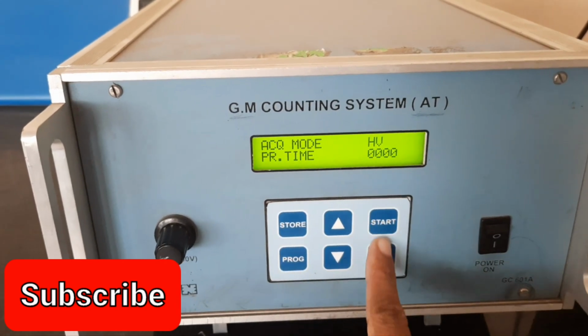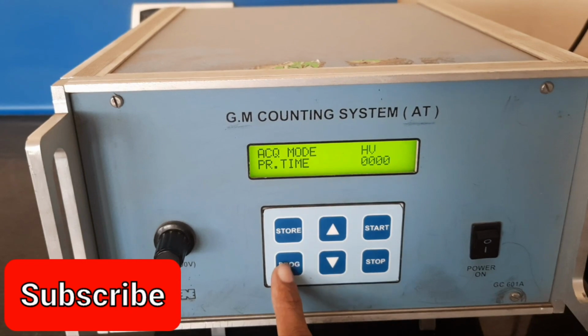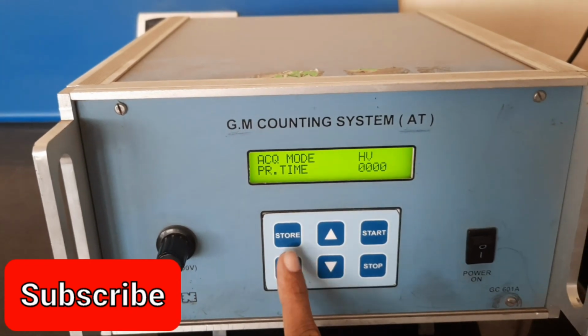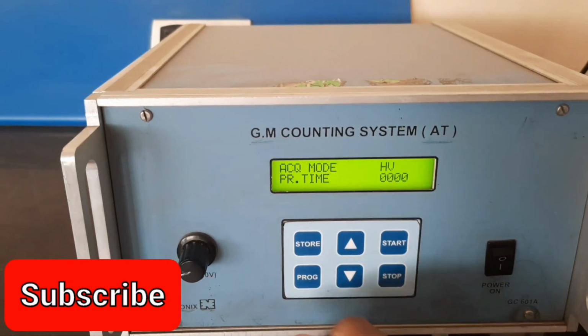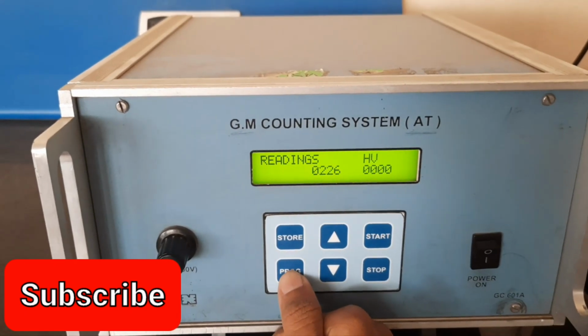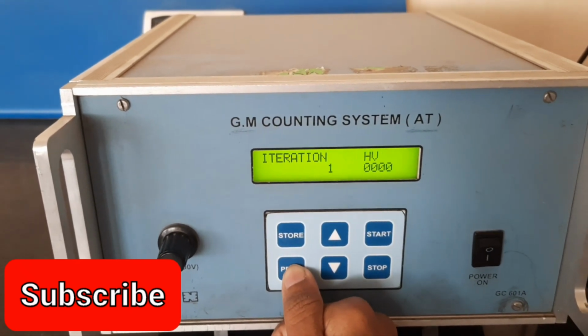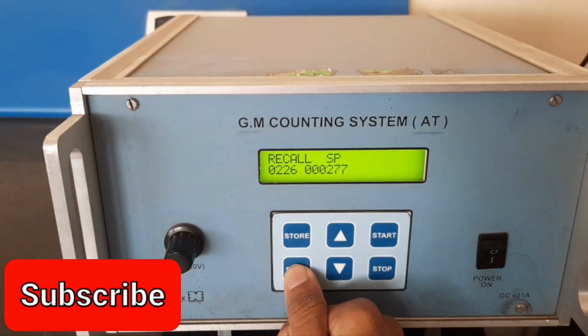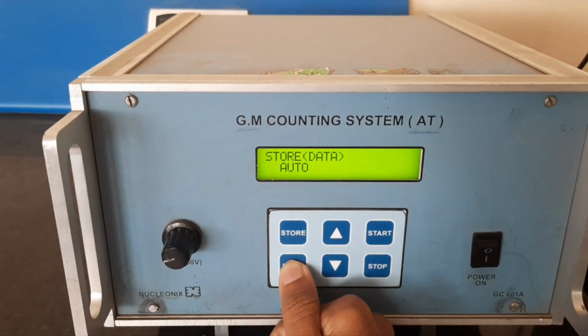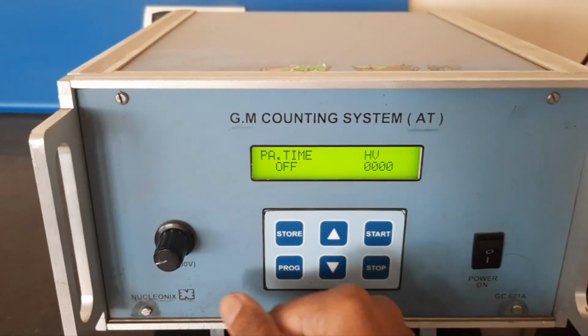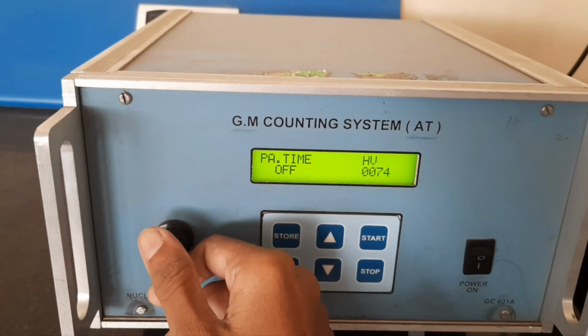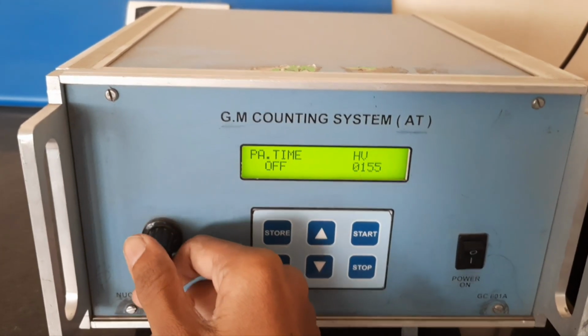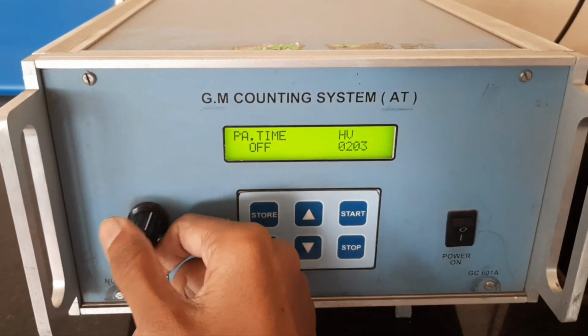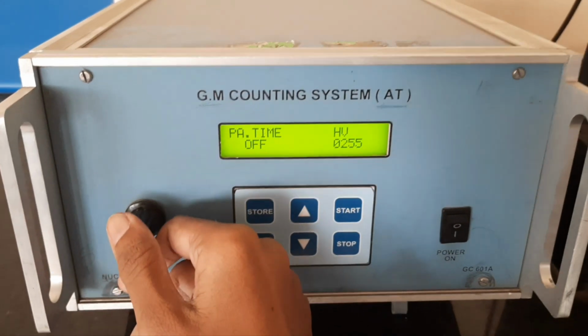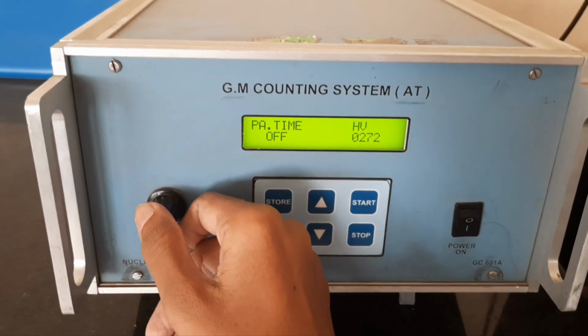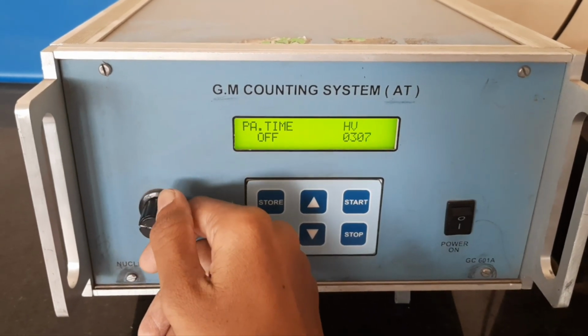I already explained how to calculate the operating voltage of a GM counter. Once you calculate the operating voltage, you can go to the program. Here you need to give the voltage as well as the preset time. The paralysis time must be off. The operating voltage of this GM counter is 550. In the previous video, I explained how to calculate it, so just watch that video; I will share the video link in the description box.